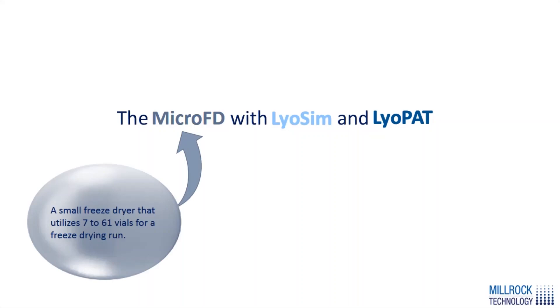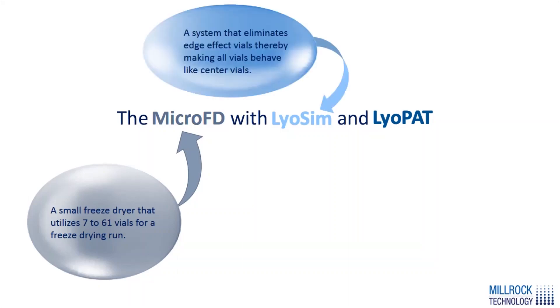The MicroFD is a small freeze dryer that can utilize between 7 to 61 vials, depending on the size of the vials, to completely develop a freeze drying run. The LyoSim is a system in the MicroFD that eliminates the edge effect, making all the vials behave like center vials, making running a small batch of vials possible and feasible.